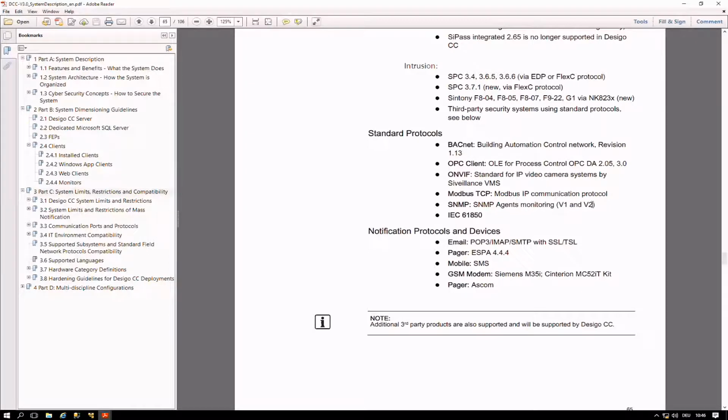The second issue was that if you started to configure, let's say 1 to 10 SNMP devices per driver, and you deleted them again, in the SNMP snap-in, in the Desigo CC snap-in, they were deleted, not in WinCC. They were kind of occupied. And then you restarted in the Desigo CC SNMP again, and you had an issue again.